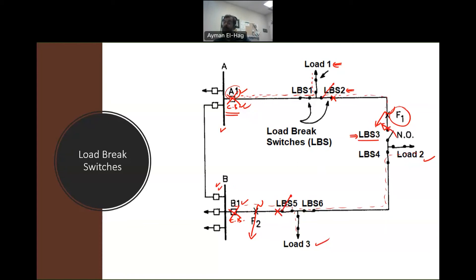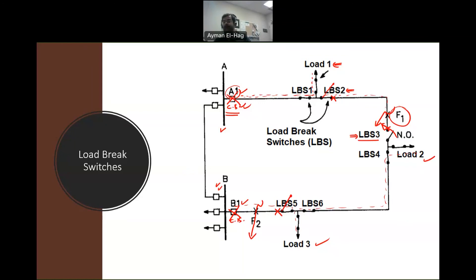Once the fault is safely isolated, we close the normally open switch LBS3. Now we can get power from the other bus — bus A — to feed loads 2 and 3. This is why it's important to design the system as a ring: in a purely radial system, a fault means no power until the fault is cleared, which could take days. The ring design with load break switches gives us the flexibility to isolate any faulty section and restore power to all customers as fast as possible.